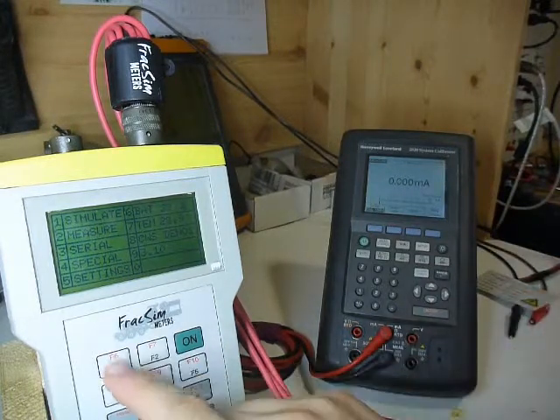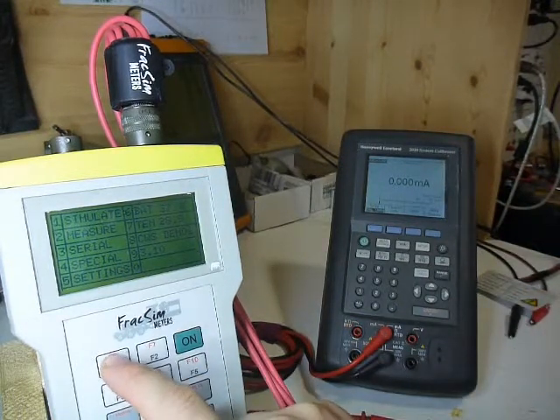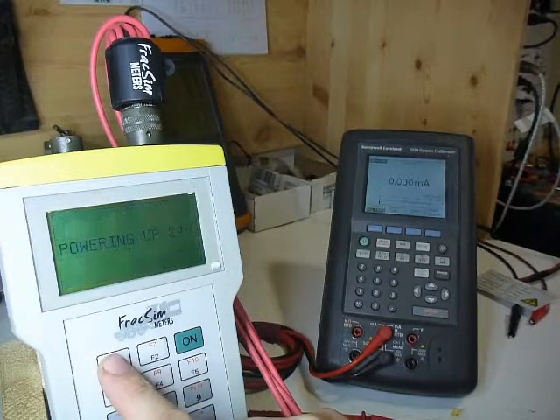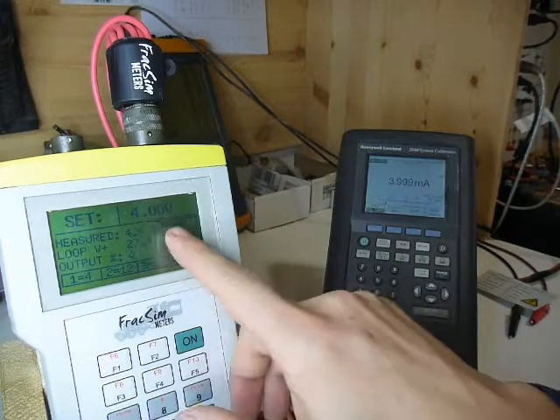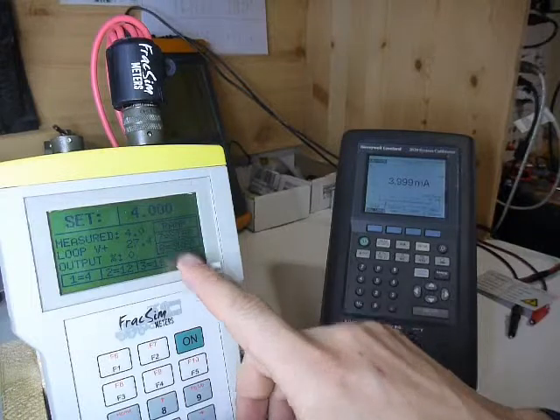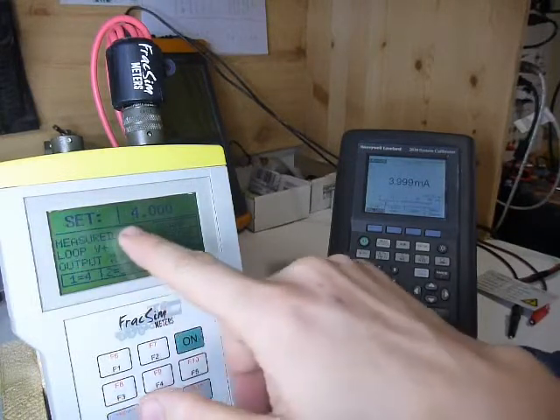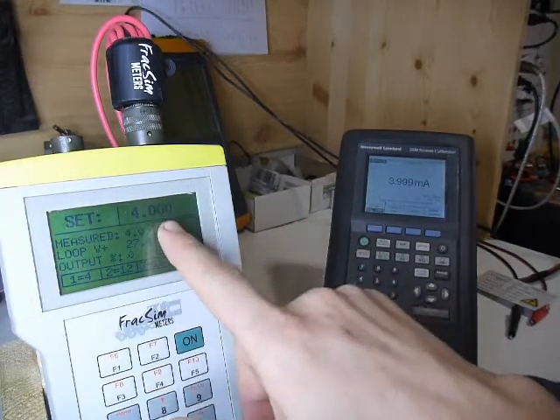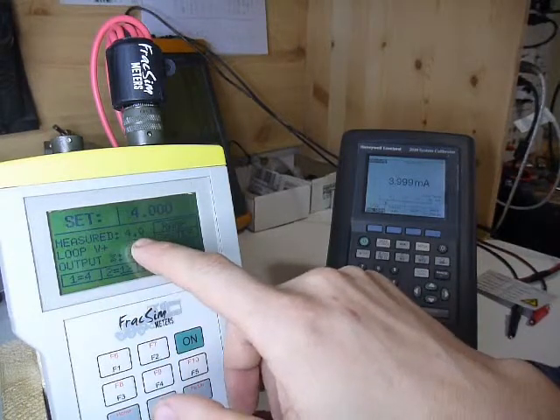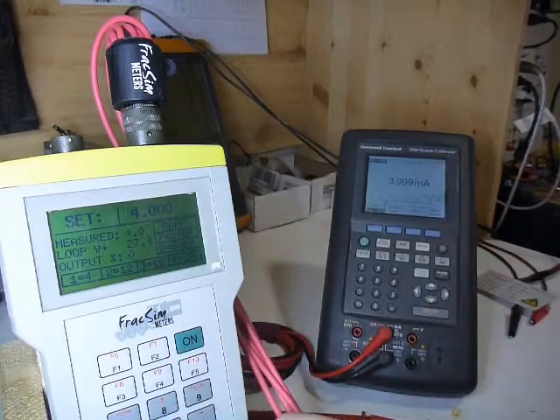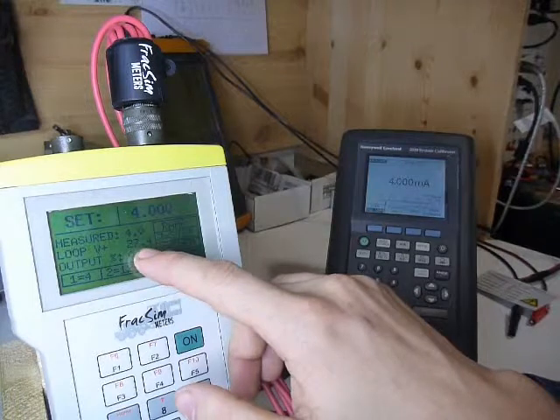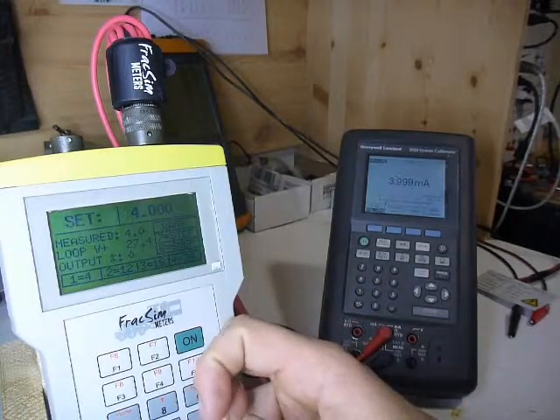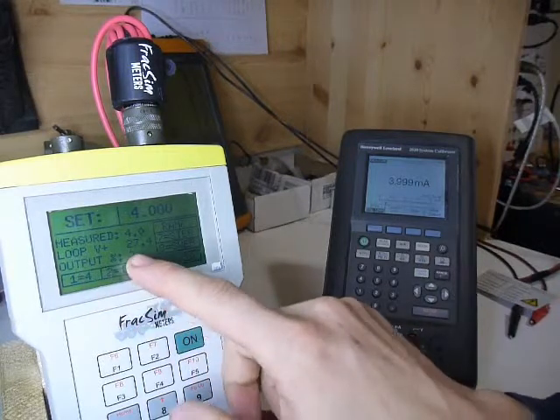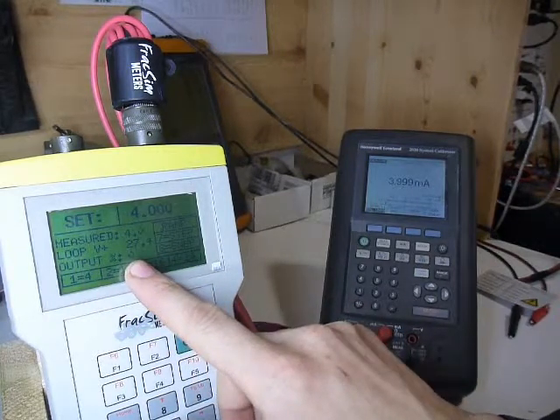And on the meter here, you would just press number 1 for simulate and number 1 for current. And it automatically starts off at 4 milliamps, and you're going to see a couple things on here. You're going to see the set, which means set point, 4 milliamps. You're going to see the measured current, and this is actually what the meter is measuring internally. And you're going to see the loop voltage. This loop voltage is internal from the meter because we are sourcing. The output percent, that percent is based on a 4 to 20 milliamp scale.